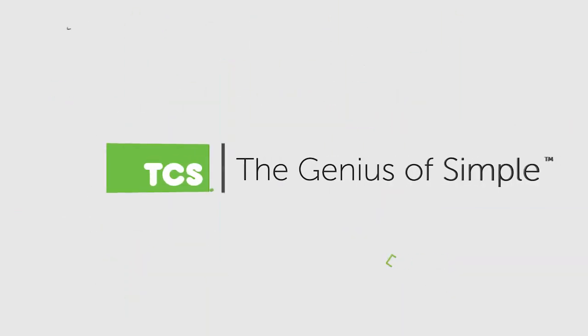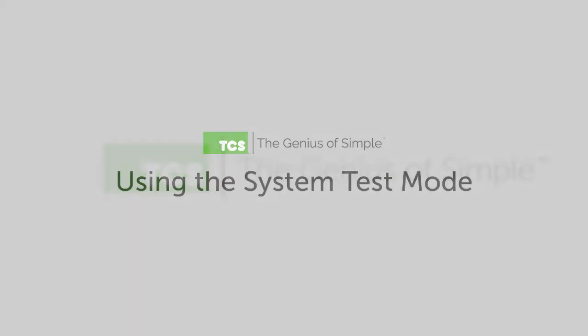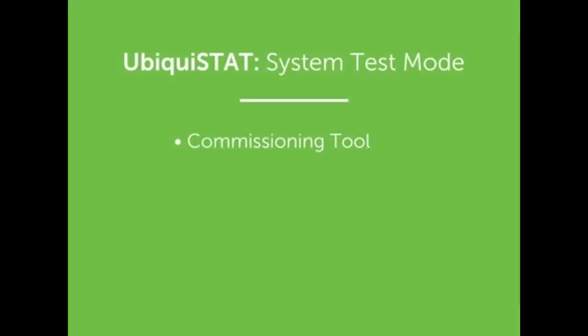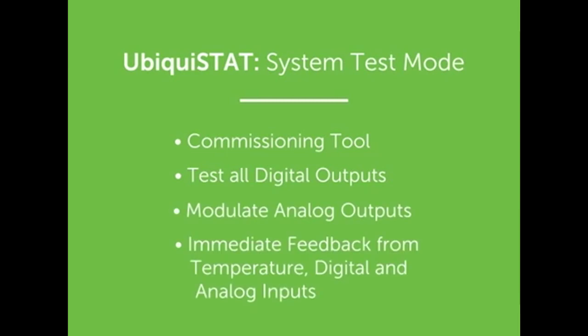In today's lesson, we will review the Ubiquistats System Test Mode. The System Test Mode is used during initial commissioning or anytime the user needs to test any digital output by cycling them on or off, or any analog output by increasing or decreasing the signal.